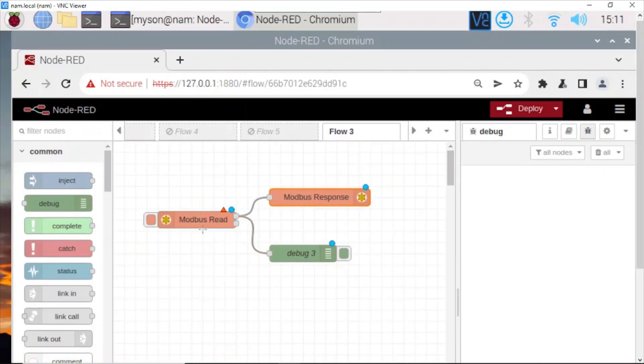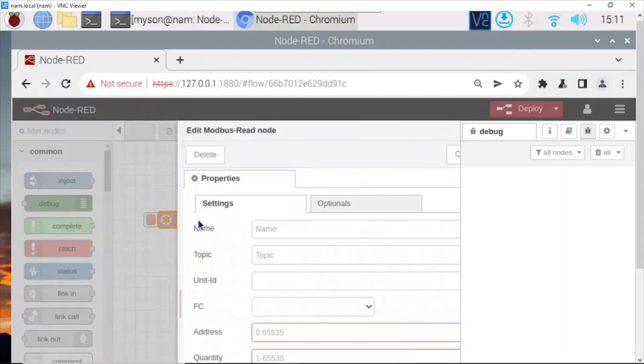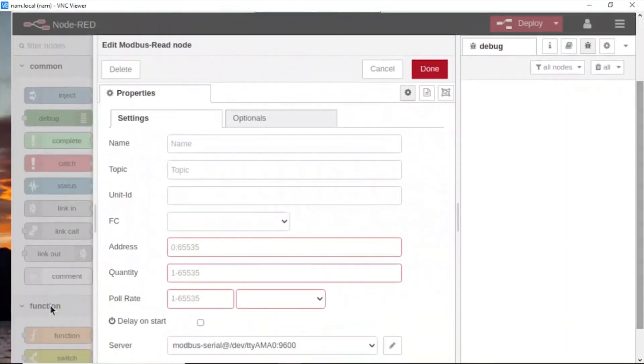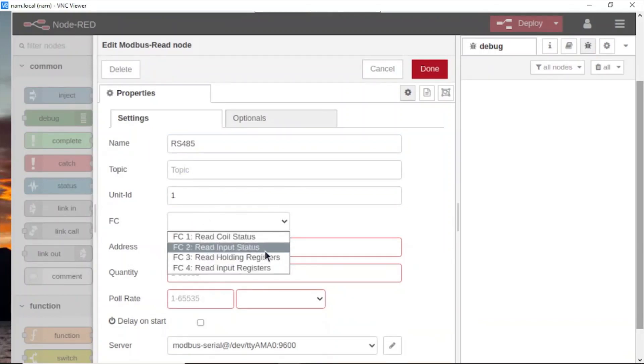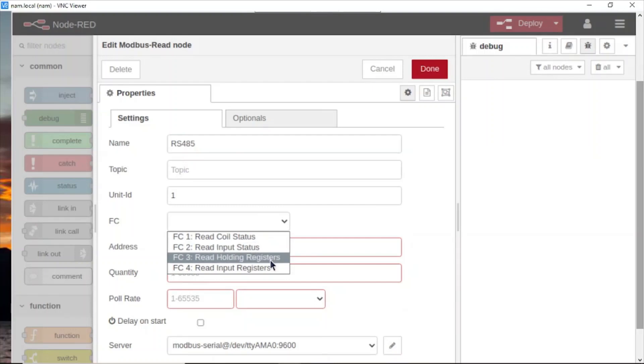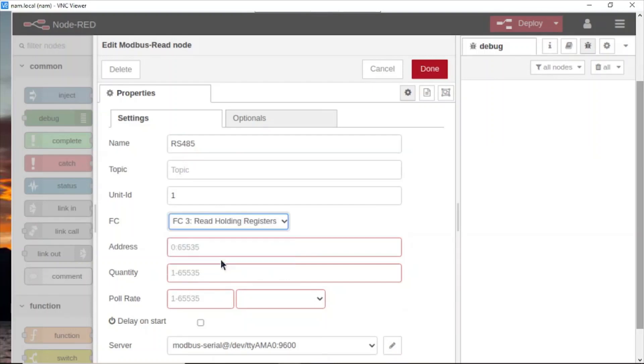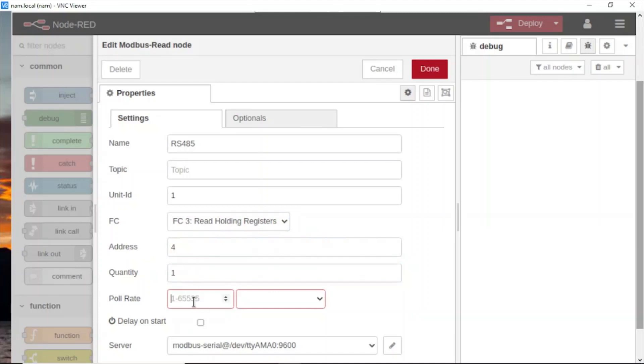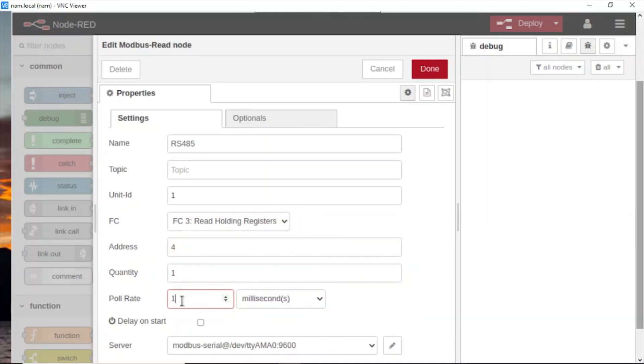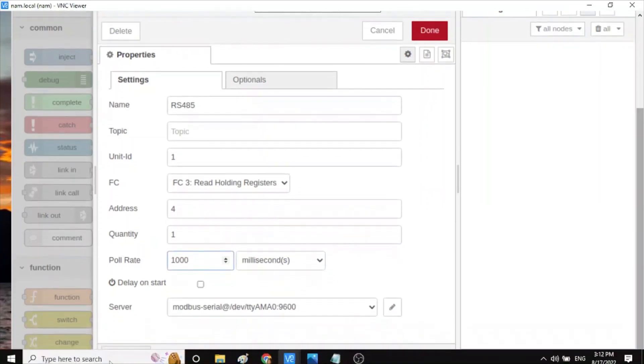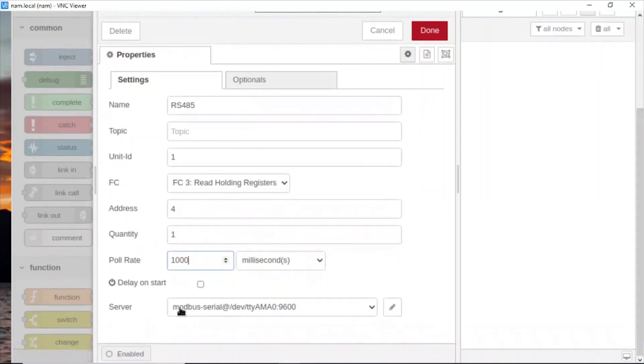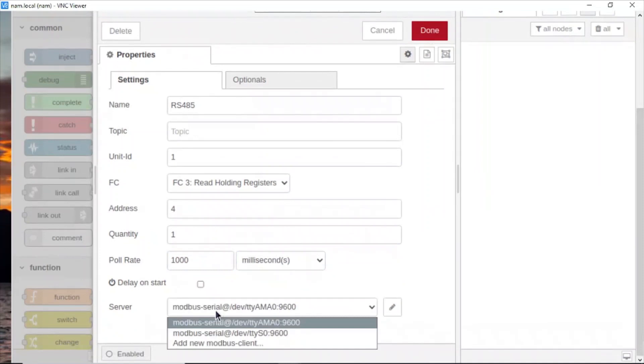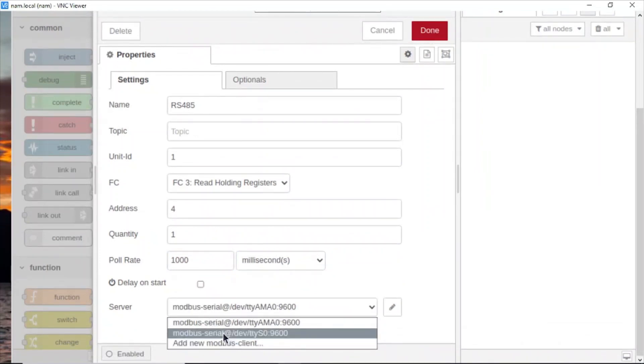Configure Modbus Read now. Name: RS-485, ID 1, read holding register or read input status, it depends on your sensor. Address: my sensor is 4. Quantity: 1, poll rate 1000. Unit ID: my server is 0. Port: here.